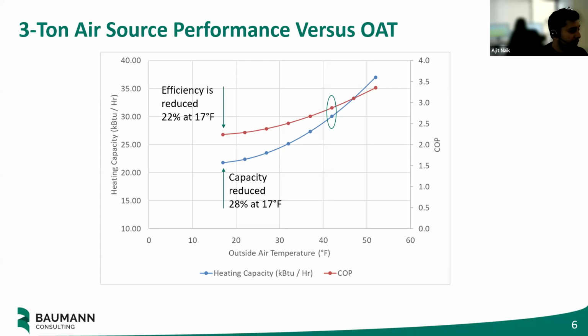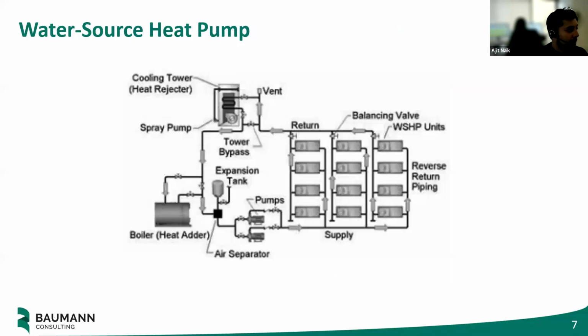So again, just a couple summaries of those numbers here. Our efficiency is reduced 22% at 17 Fahrenheit. Our capacity is reduced 28% at 17 Fahrenheit. And the crossover point where it becomes less damaging to the environment to actually use gas than an air source heat pump is also indicated as well. This brings up other technologies. Do we have to take the heat from the air?